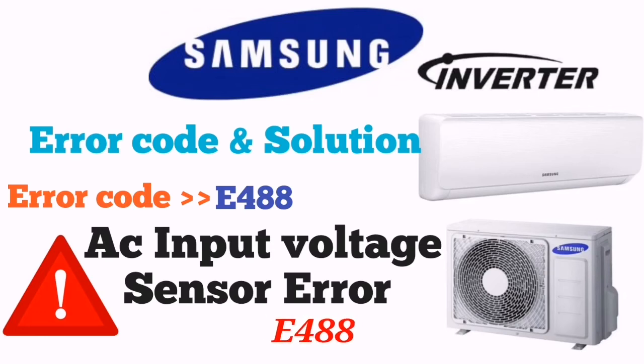in normal operating mode. The normal range should be 0.2 volt DC to 4.8 volt DC, and if it's not showing the voltage correctly, then you have to change the PCB. And if the voltage is correct, then you have to check if the reactor insulation is damaged or not. If it is not damaged, again you have to change the outdoor PCB and check if it is working or not. Even if it is not working, then you have to change the reactor and your unit will be in working condition.